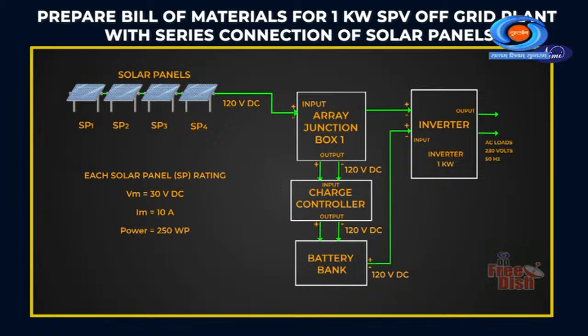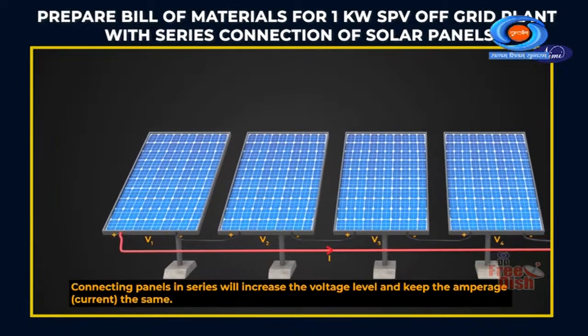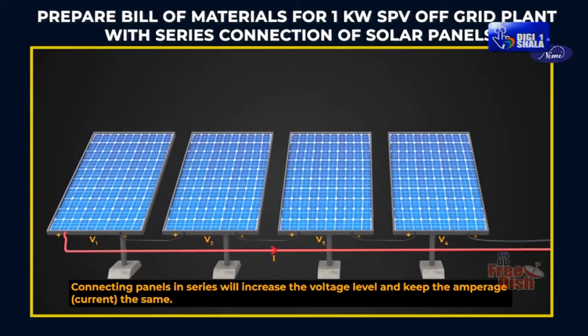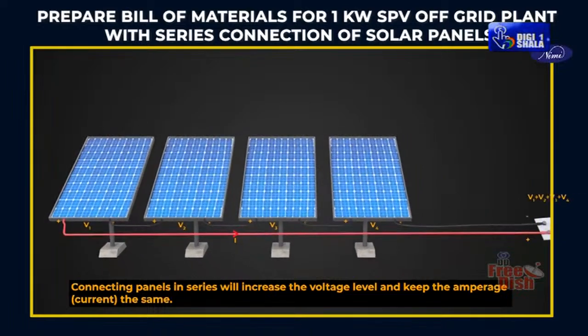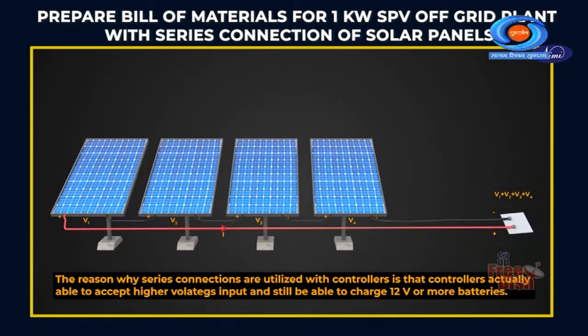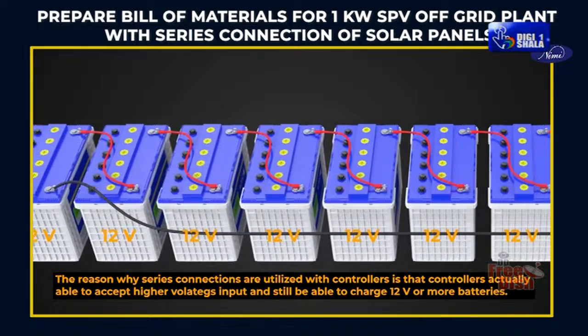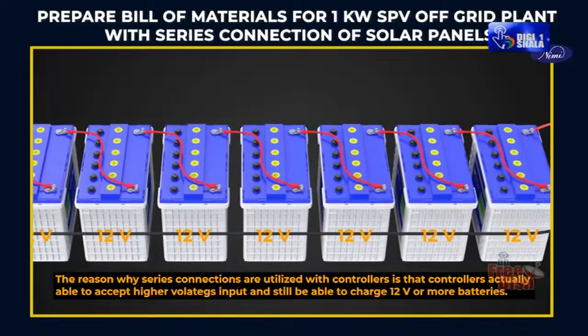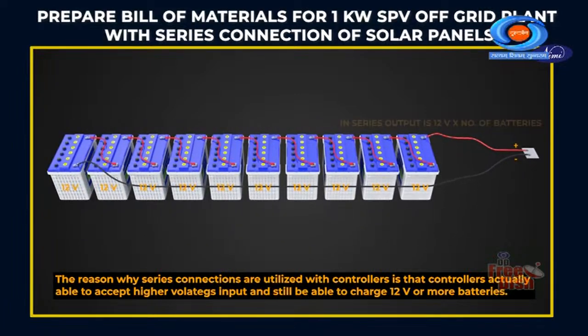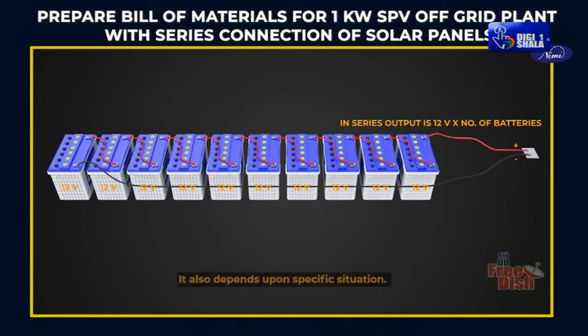Prepare a bill of materials for a 1 kilowatt solar photovoltaic off-grid plant with series connection of solar panels. Connecting panels in series will increase the voltage level and keep the amperage, that is, the current, the same. The reason why series connections are utilized with controllers is that controllers are able to accept higher voltage input and still be able to charge 12 volt or higher batteries. It also depends upon the specific situation.